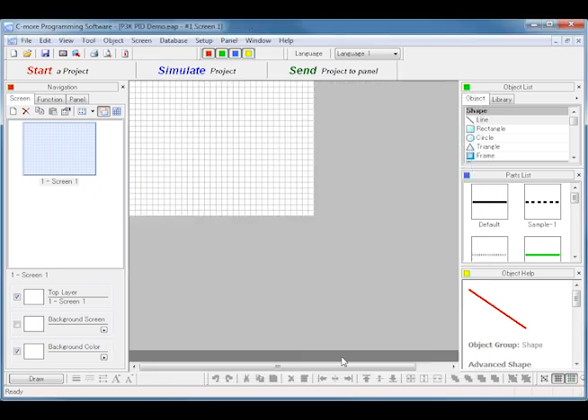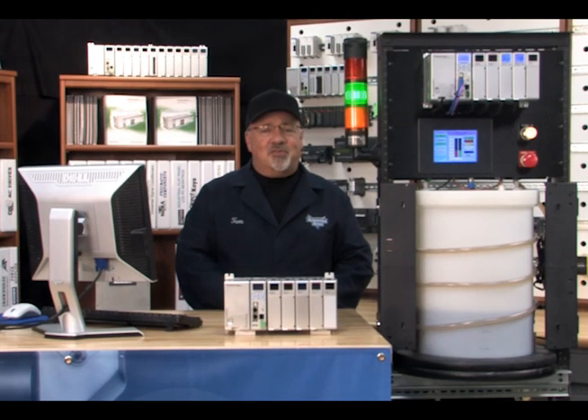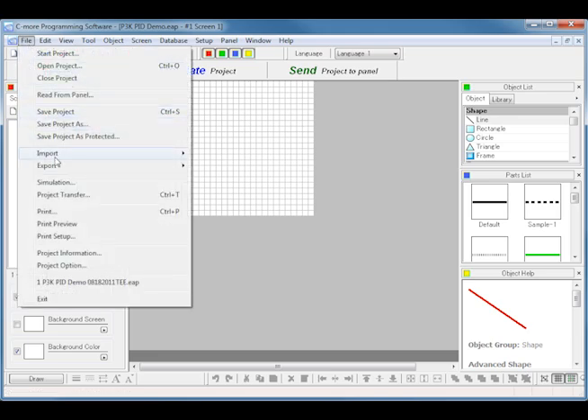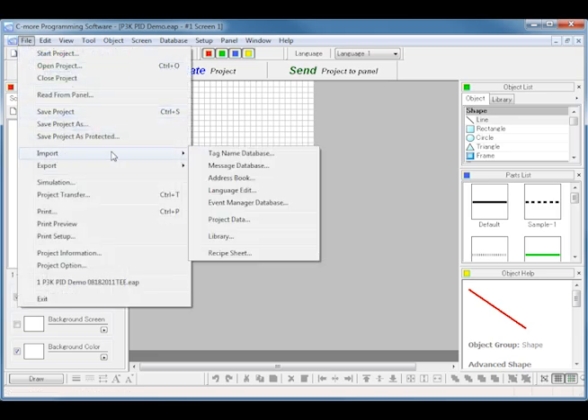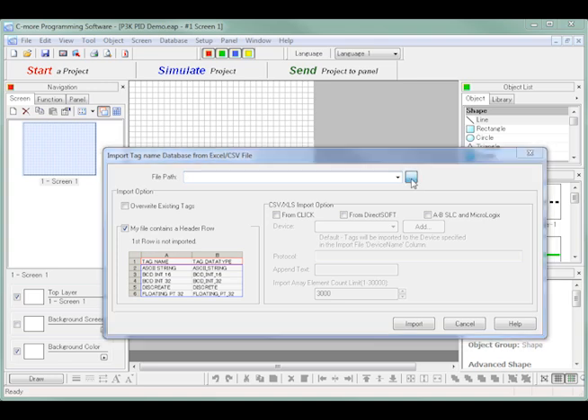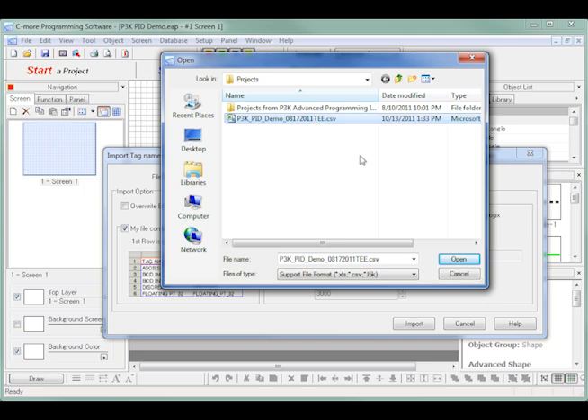I can now import my tag names from the CSV file that I exported earlier from the Productivity 3000 programming software. I click on Import under the File pull-down menu and slide my pointer to Tag Name Database. This will open the Import Tag Name Database from Excel CSV File dialog box. I click on the Browse icon to the right of the File Path drop-down box and select the CSV file that I exported earlier from the Productivity 3000 software.